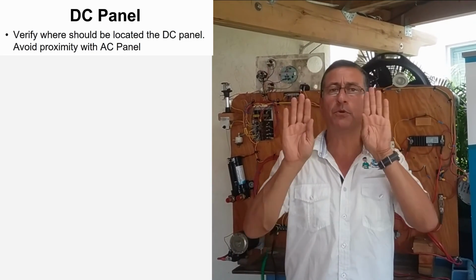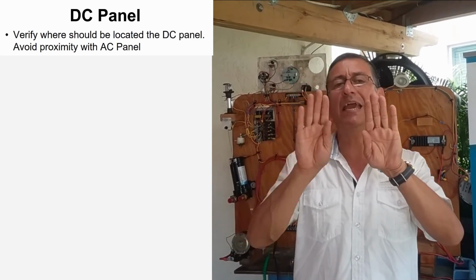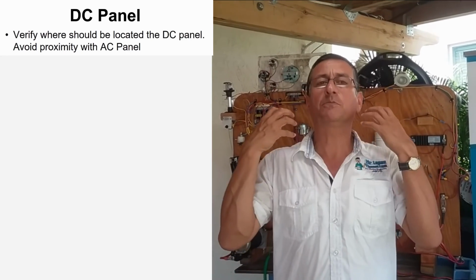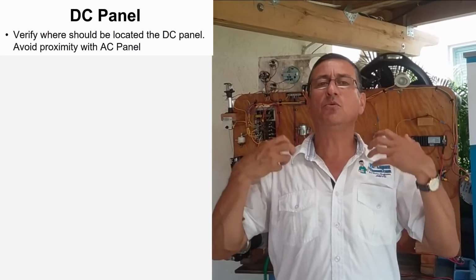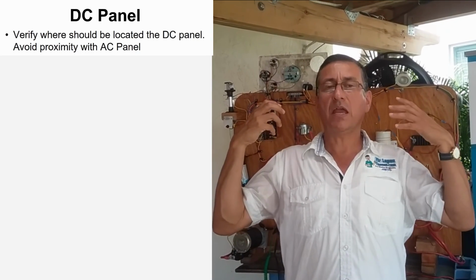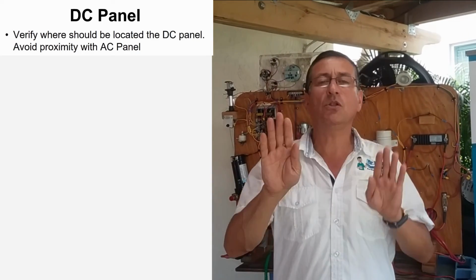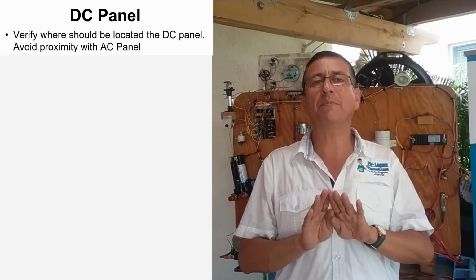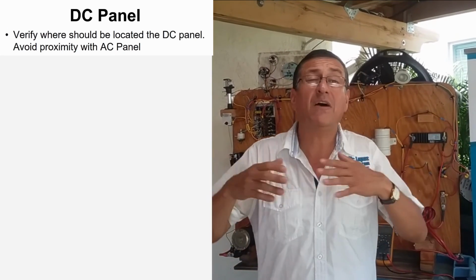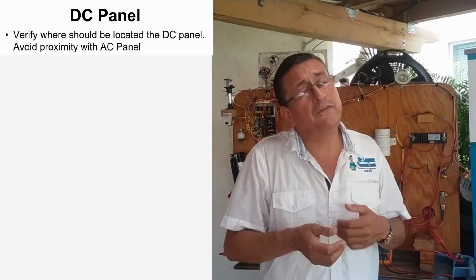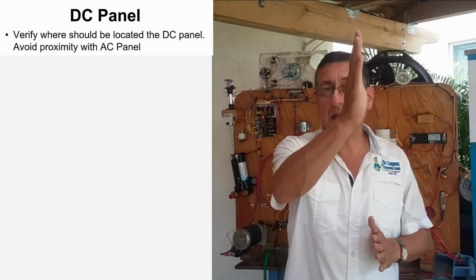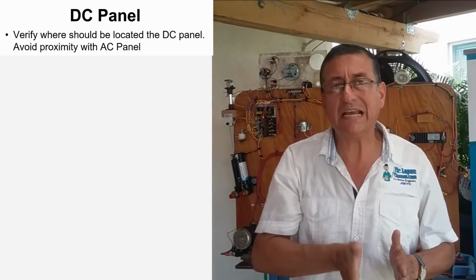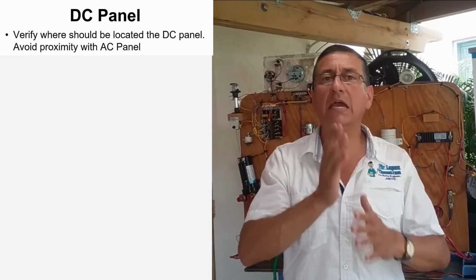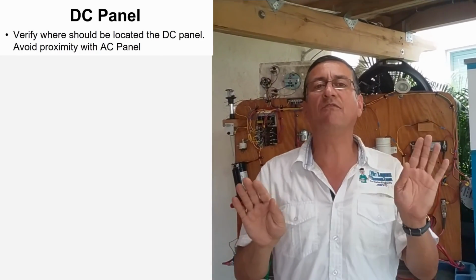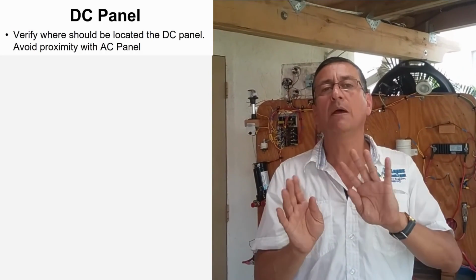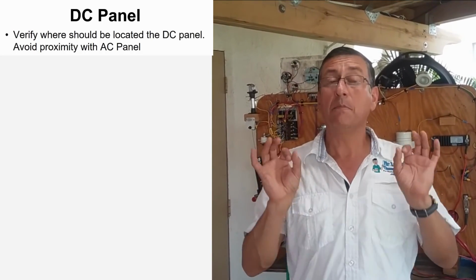Try to avoid proximity between the DC panel and the AC panel. Try to explain to other contractors, to the customer, to the captain, that locating them together in the same compartment is not recommended. If at the end of the day that's the only possibility, you need to separate both of them with a special insulation material, bakelite or fiberglass, in order to avoid cables passing from one side to the other. Be careful with that.